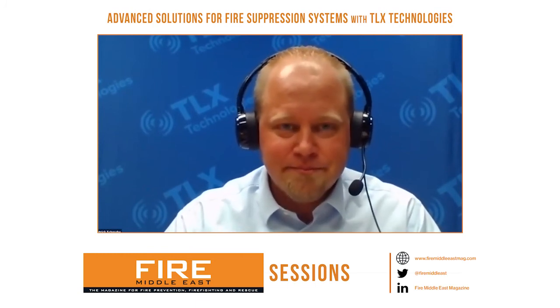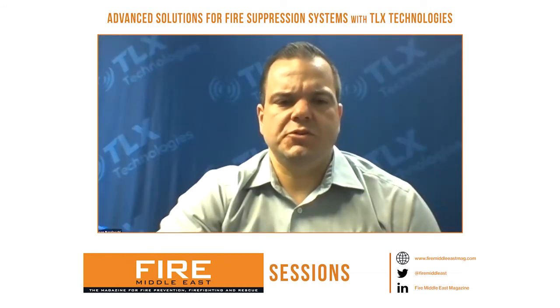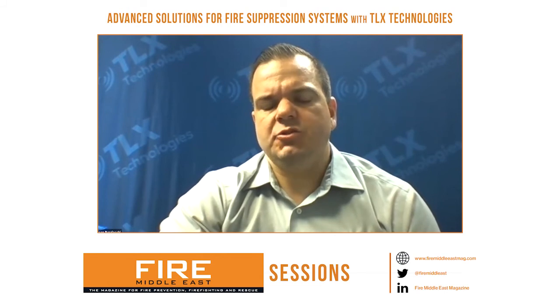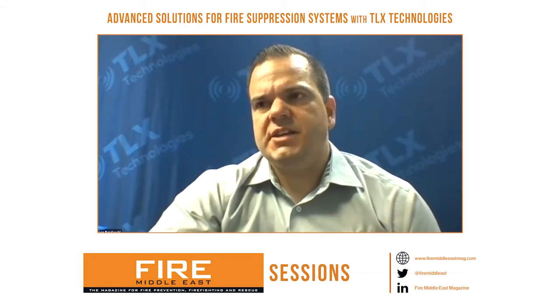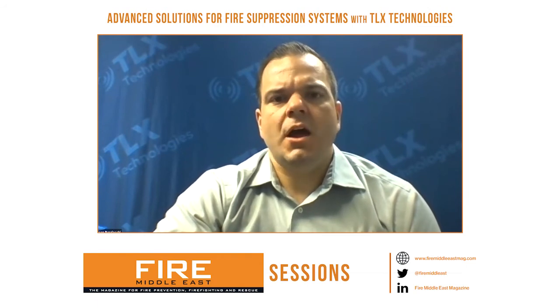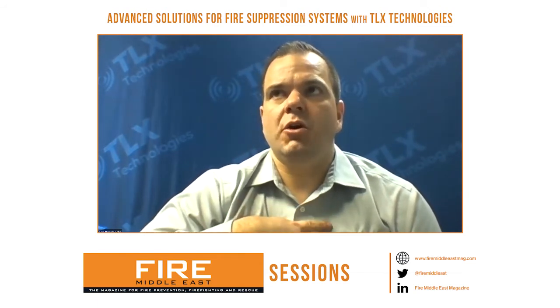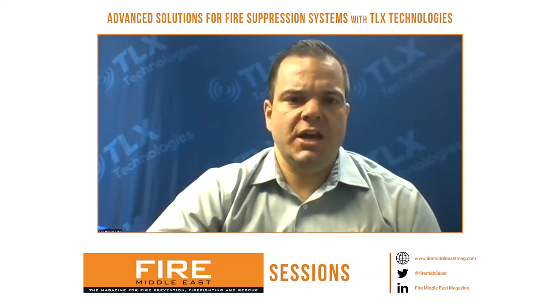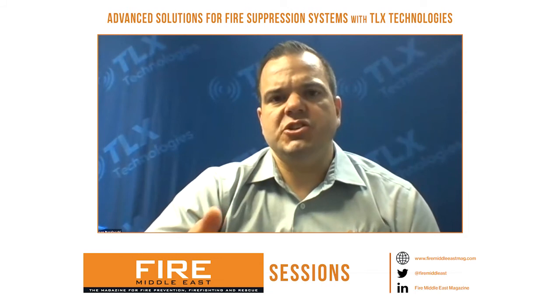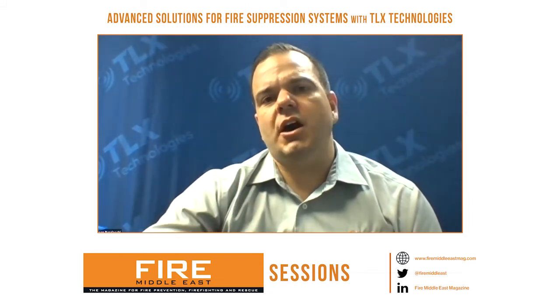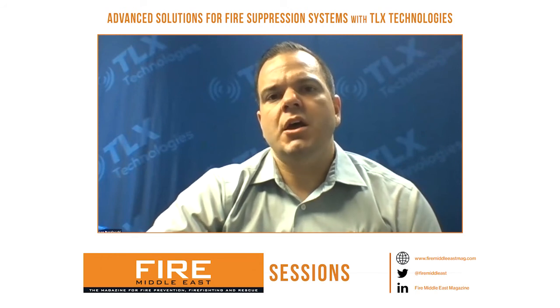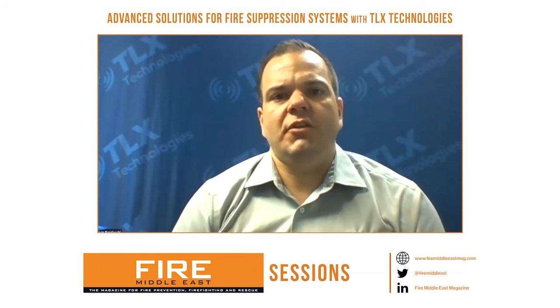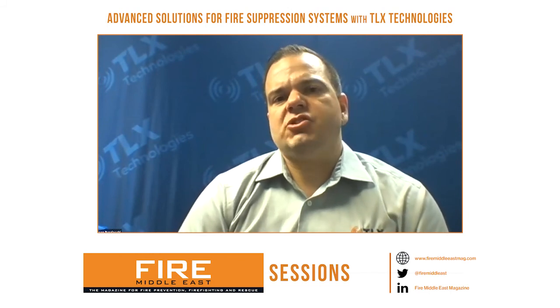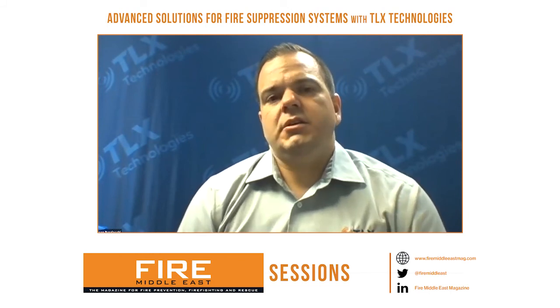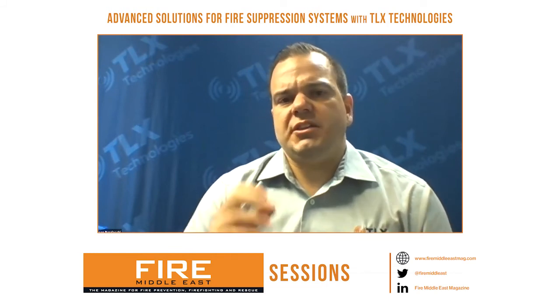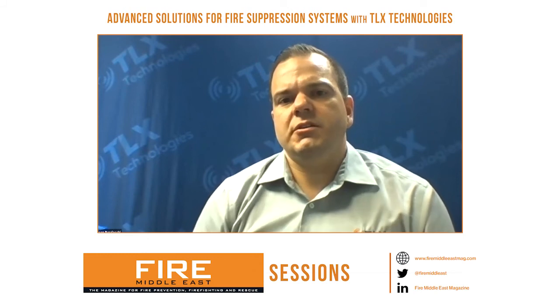And reassuring. One more thing, as we were sitting here I quickly looked up the NFPA 12 code. That's a code dictated on carbon dioxide systems. Our particular components, while they're compliant to certain NFPA codes, that's why we added the supervision device within our components, so it helps our customers comply to NFPA 2001. There is no actual requirement for us to do that outside of what's requested by UL. So our devices comply at the component level to UL 864.